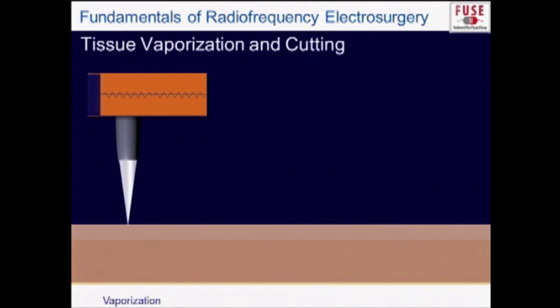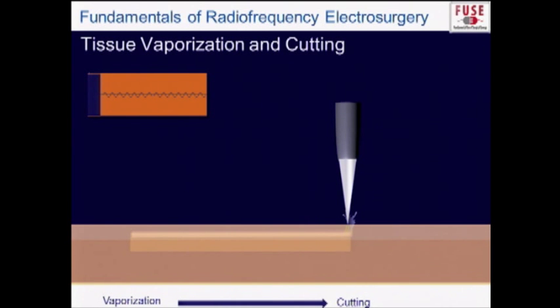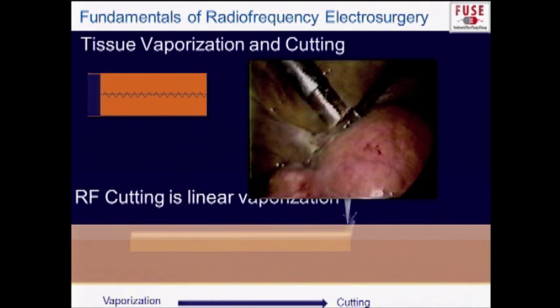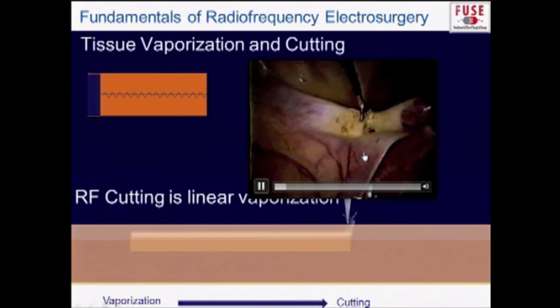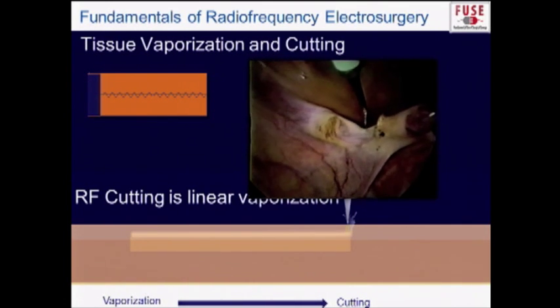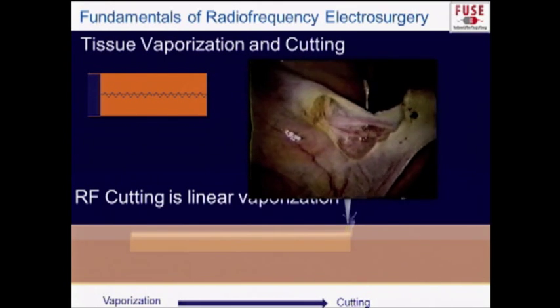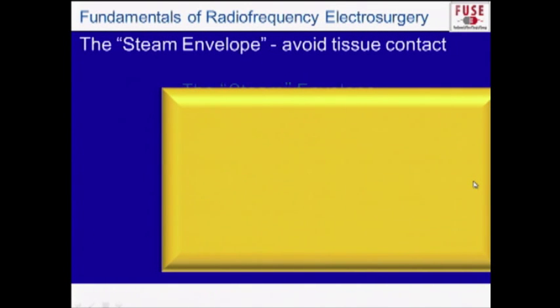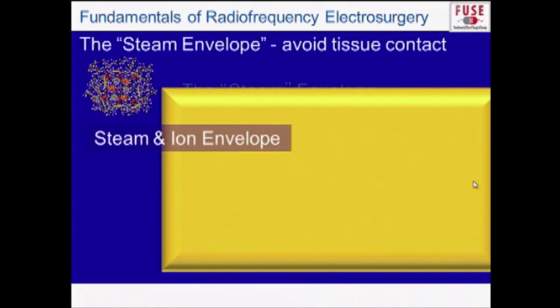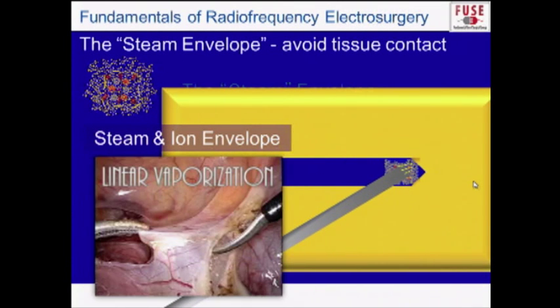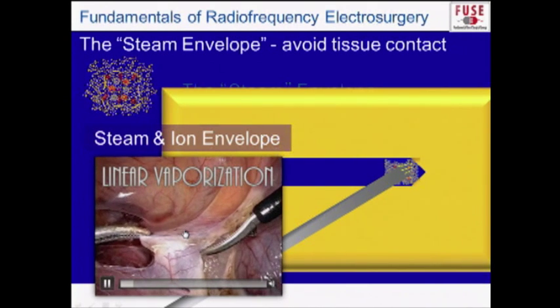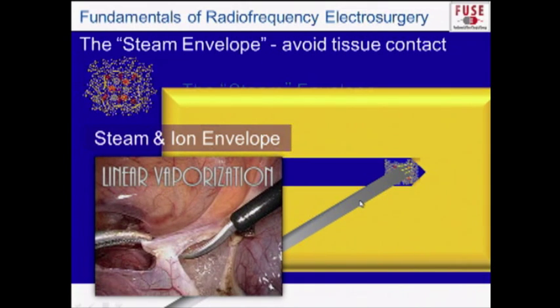How does vaporization or cutting actually work? The electrode is placed very near the tissue, activated to create a steam envelope, then extended linearly — cutting is linear vaporization. The electrode stays within that steam or vapor envelope, which has abundant ions and very low impedance. A hook electrode is shown vaporizing in non-contact mode with very little thermal spread to adjacent tissue.